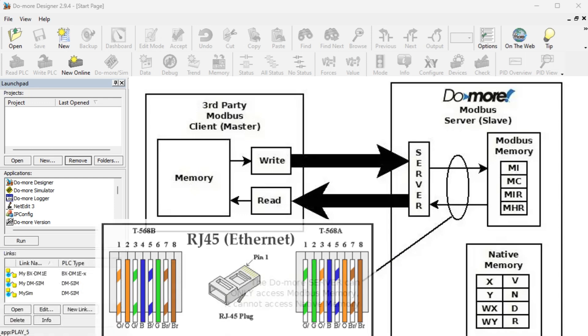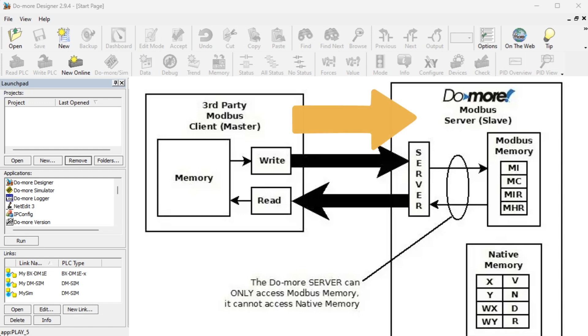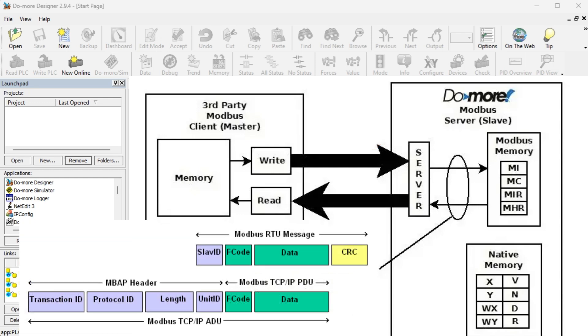Ethernet communication will use an RJ-45 media; the CAT Ethernet cable used will depend on the actual network and location. Modbus TCP protocol is used on this network. Modbus is a master/client to slave/server protocol. In a serial environment there can only be one master or client, and the slaves or servers will respond only when data is requested. In an Ethernet environment, multiple clients can be used, ensuring that simultaneous commands are handled in order.